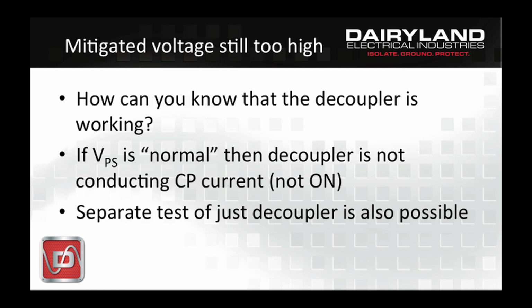One last slide. People will ask how they can know if the decoupler is working. And there are specific tests that can be done just with the decoupler itself as a pass-fail test. However, the simplest test you can perform is one you already do, and that is taking a normal pipe-to-soil voltage reading and determining if that represents a typical or reasonable or normal reading.